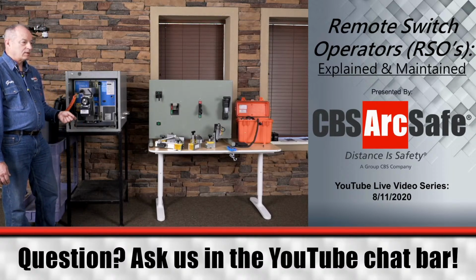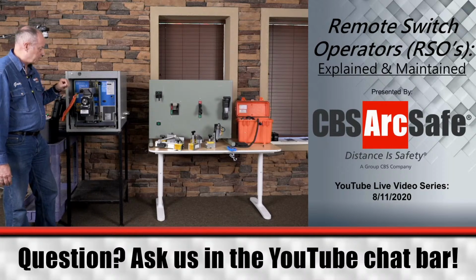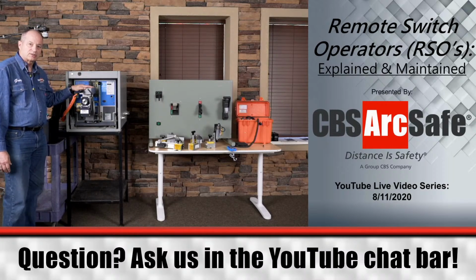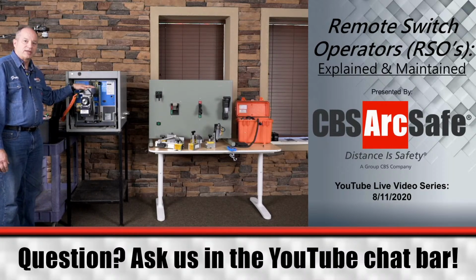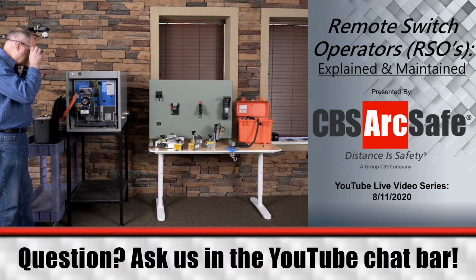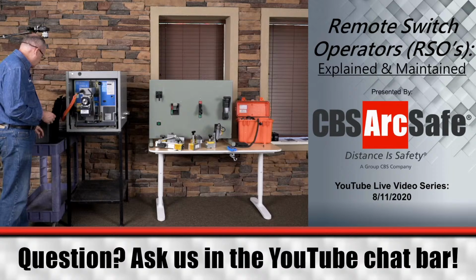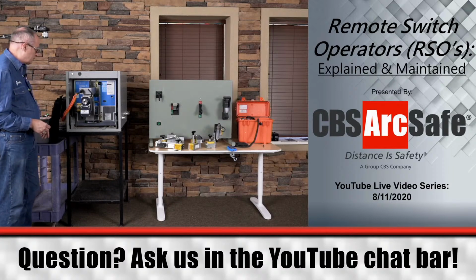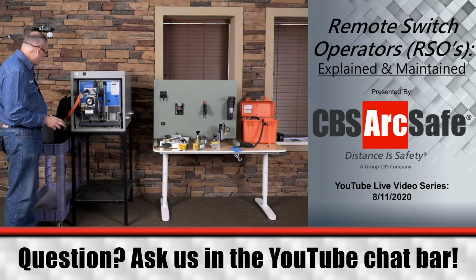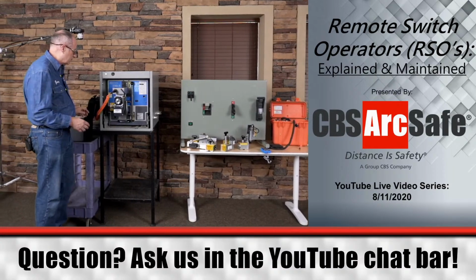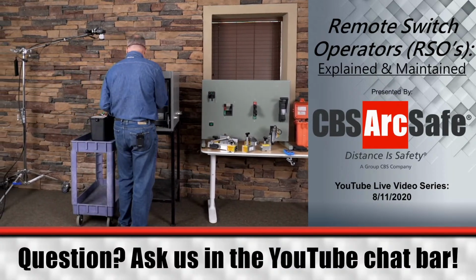Just to talk real quick, if we're looking at an RS-3 device, we've worked with the breakers to give you a recommended set of settings so you know what should be used. Now, the RS-3 systems actually have two protections. There's the electronic protection of the current control module here. I'm going to take the RS-3 off the breaker here.